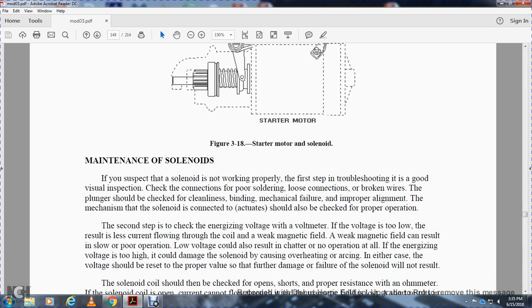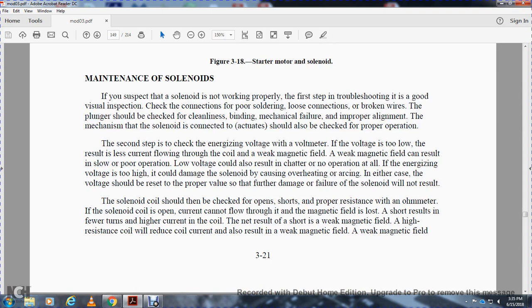Starter motor. Maintenance of solenoids. If you suspect that a solenoid is not working properly, the first step of troubleshooting is a good visual inspection, checking for poor soldering, loose connections, and broken wires. The plunger should be checked for cleanliness, binding, mechanical failure, and proper alignment. The mechanism connected to the solenoid actuator should always be checked for proper operation.